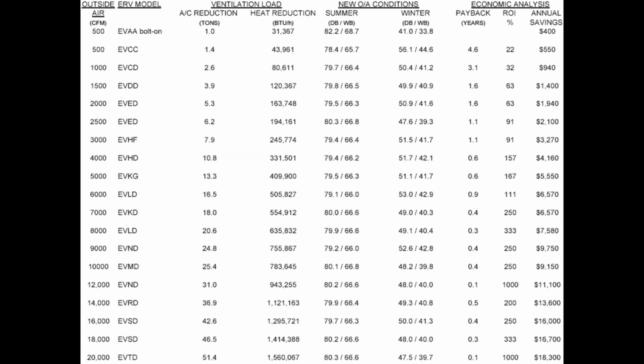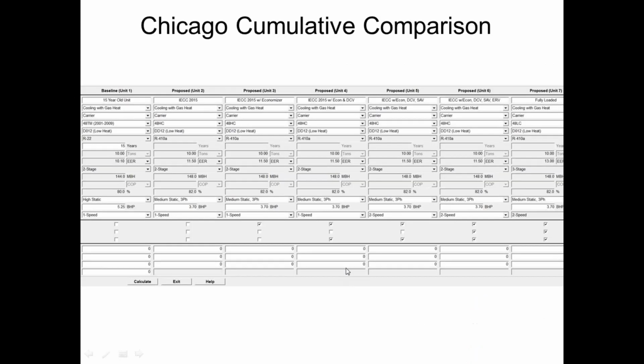So we use charts like this all the time, and we also do calculations for very specific systems. But usually the cutoff is if I get more than 1,500 CFM of outside air, the payback column starts looking really attractive for ERVs on rooftops. And this particular chart in its entirety was developed with rooftop examples. So smaller CFM outdoor units, not so great. When I get to the larger CFM, 1,500 and up, the paybacks all tend to be under 2 years, right? They get really attractive really fast. But we'll save that for another discussion.